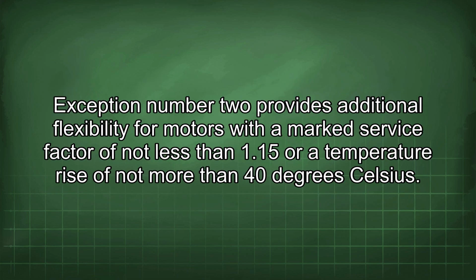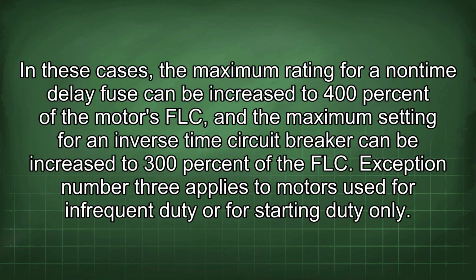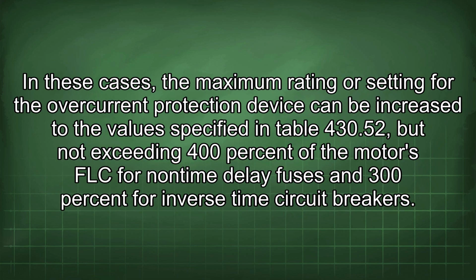Exception number 2 provides additional flexibility for motors with the marked service factor of not less than 1.15 or a temperature rise of not more than 40 degrees Celsius. In these cases, the maximum rating for a non-time delay fuse can be increased to 400% of the motor's FLC, and the maximum setting for an inverse time circuit breaker can be increased to 300% of the FLC. Exception number 3 applies to motors used for infrequent duty or for starting duty only. In these cases, the maximum rating or setting for the overcurrent protection device can be increased to the values specified in Table 430.52, but not exceeding 400% of the motor's FLC for non-time delay fuses and 300% for inverse time circuit breakers.